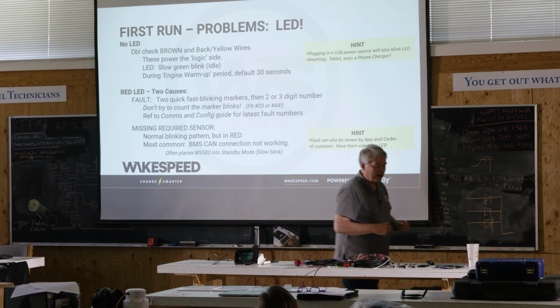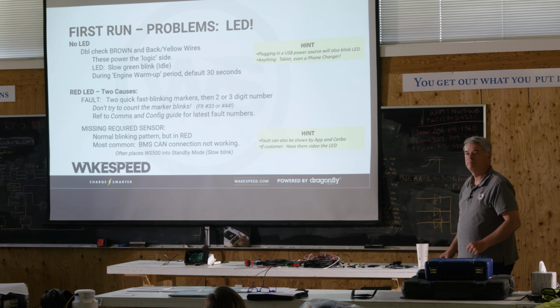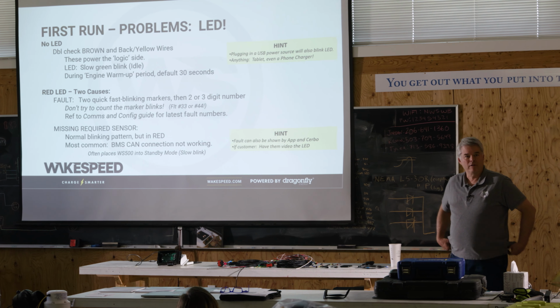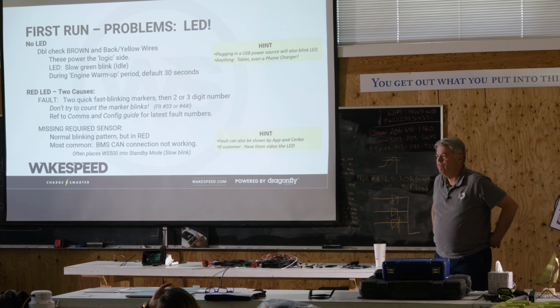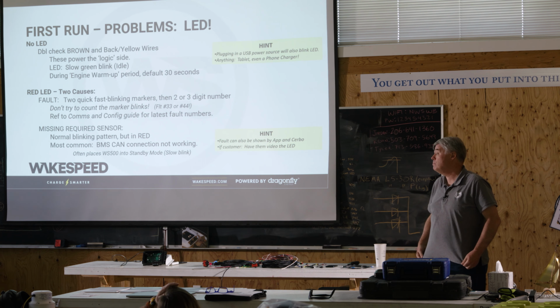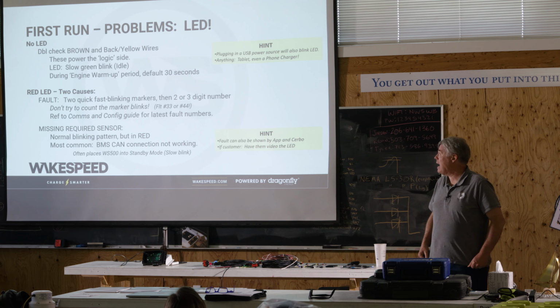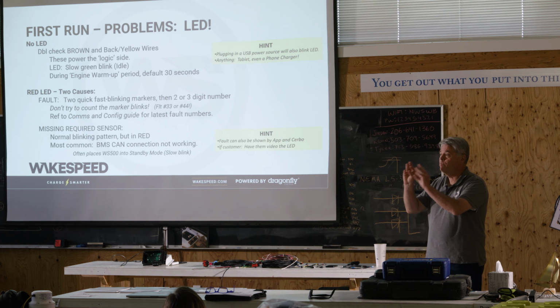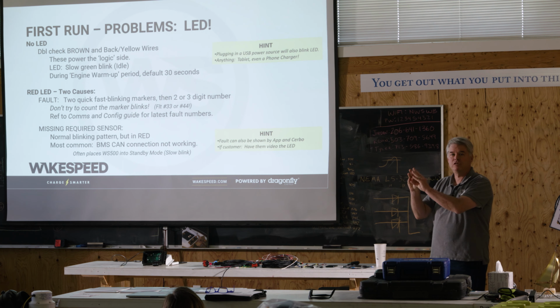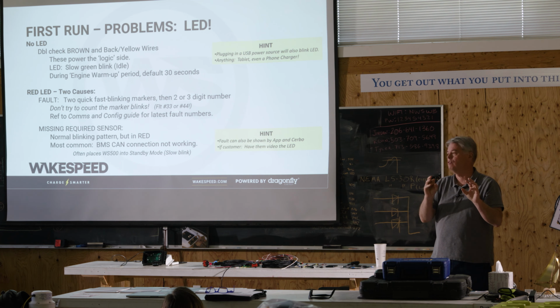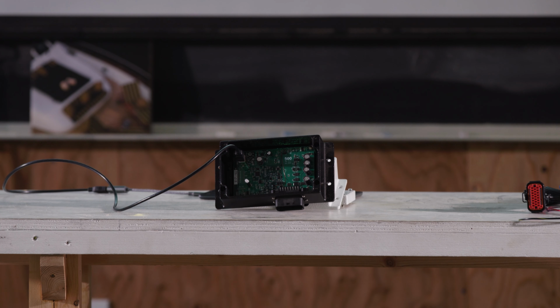The regulator is starting up, doing its blinking green. After about 30 seconds, it goes into a fault, meaning it can't see battery voltage. The pattern is 2 bursts of quick blinks, then it blinks out the fault number, a 2-digit number. Don't count the bursts. When we get a support call saying 'I have a fault 44,' that means you're an overachiever, counting bursts. Don't count the bursts, I'm not that cruel.